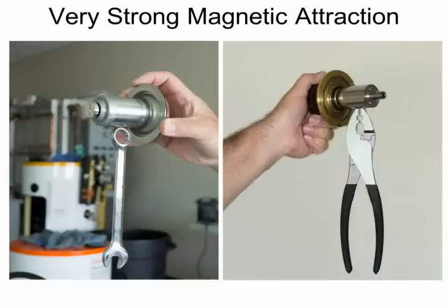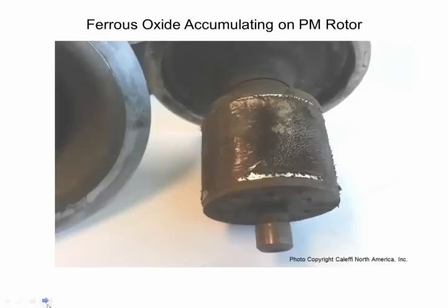And if you take these rotors out of these pumps, you can see the effect of those permanent magnets. They're extremely strong. Okay, so here we got a couple different pump makes, and Kevin here put tools on it and show basically how strong these are. Really strong. In fact, I think Kevin was missing some fillings that night, unexplainably. So the permanent magnets, that attraction, you pull out a rotor from a permanent magnet that has a lot of ferrous oxide in the system, you might see something like this here, where basically that magnetic field has attracted that ferrous oxide and accumulated on the rotor as it spins around in the volute or inside of the canister here.